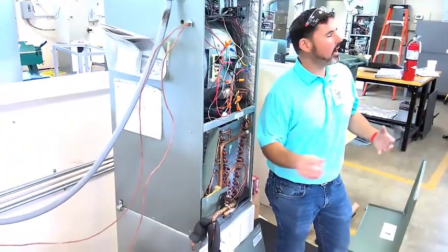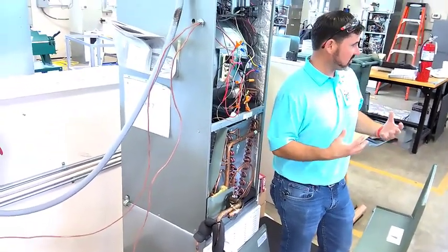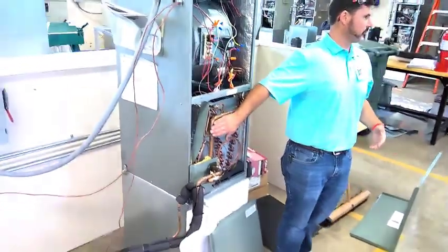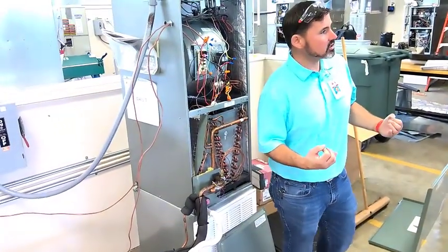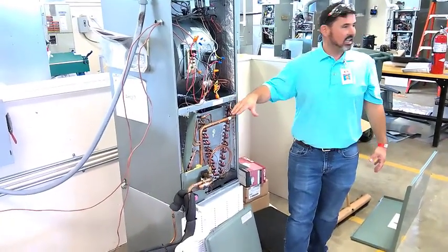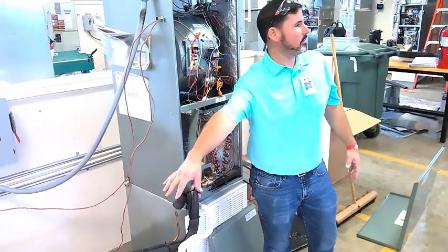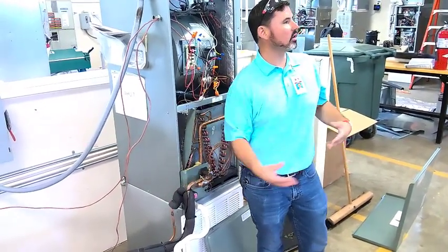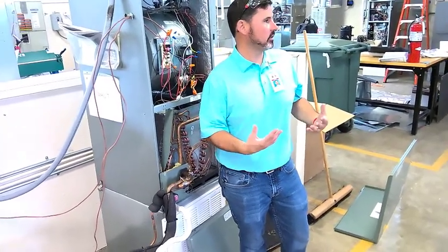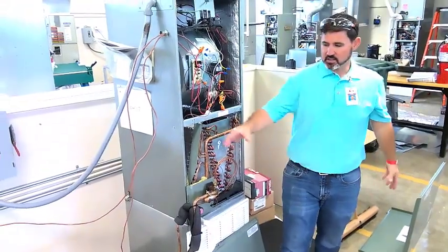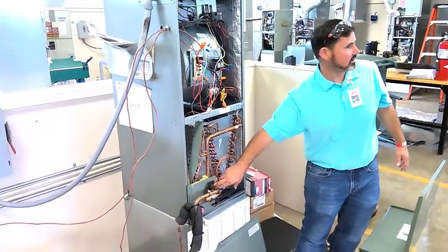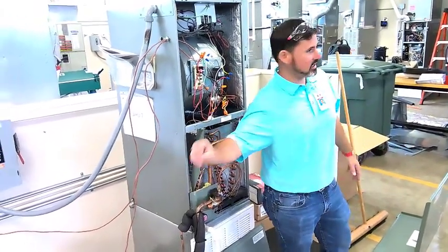A compressor cannot pump liquid. You'll damage your compressor if I send liquid back. That's why I need to make sure I have some superheat. I don't want too much superheat because that means, one, I'm not using my whole evaporator coil to absorb heat. And two, I'm going to have hot gas or warm gas coming to that compressor. Most compressors are cooled off by the refrigerant itself. So if it doesn't have cool vapor coming back to it, that compressor may overheat. So that's our basic refrigeration cycle: compressor, discharge line, condenser, liquid line, metering device, evaporator, suction line, back to the compressor.